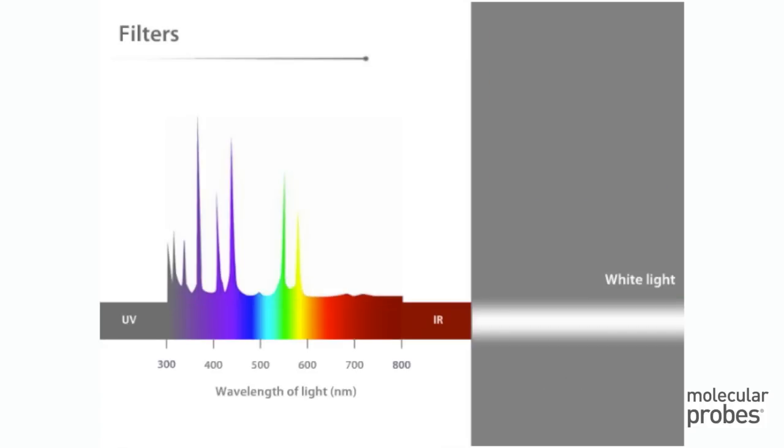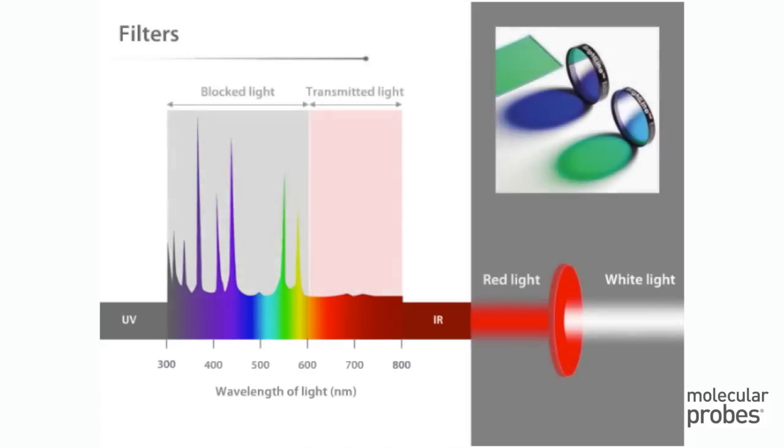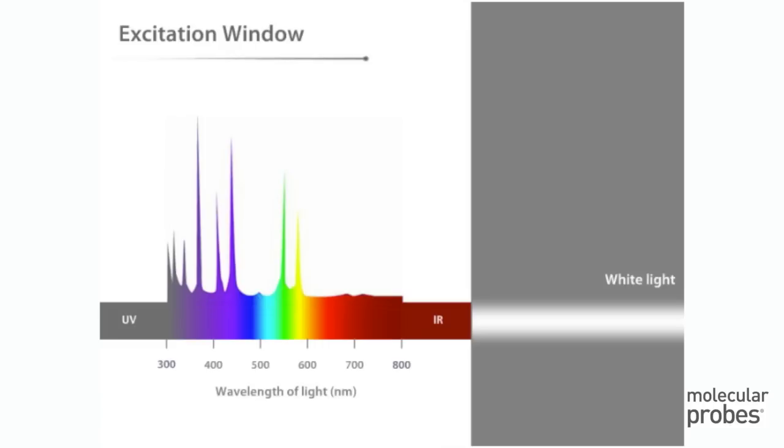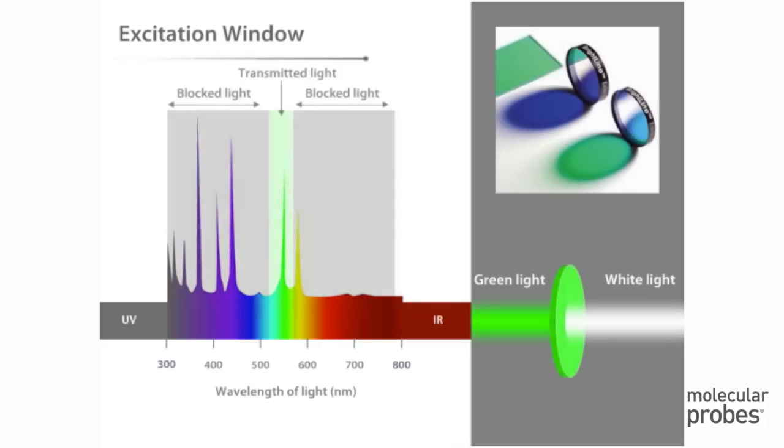When using broadband white light sources, it is necessary to filter the desired wavelengths needed for excitation. This is most often done using optical filters. Optical filters can range from simple colored glass to highly engineered interference filters that selectively allow light of certain wavelengths to pass, while blocking out undesirable wavelengths. For selective excitation, a filter that transmits a narrow range of wavelengths is typically used. Such a filter is called a bandpass excitation filter.